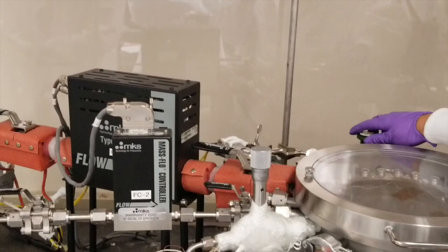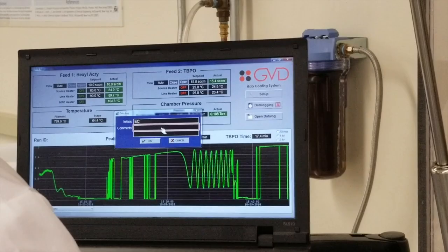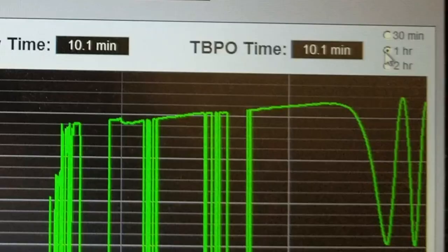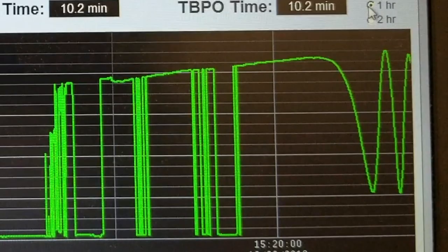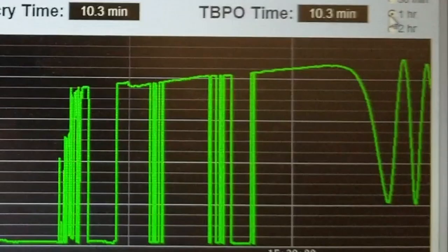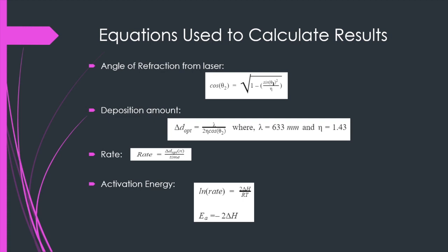As one of our teammates gets ready to close the nitrogen valve we start data logging and begin the desired flow by pressing auto on the program. Once we start seeing sinusoidal curves that is when the run begins. We know it's complete after 3 to 5 waves and to count the waves we start from the first low point in the wave. When the run is complete we stop data logging, turn off the heater, stop the flow, close the valve, and turn off the chiller.